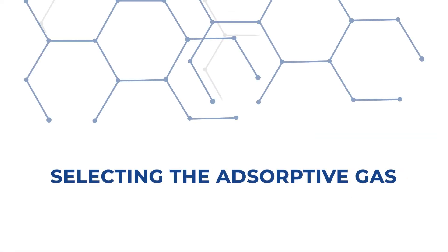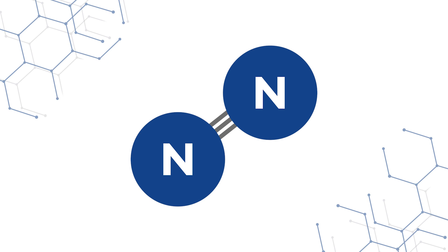Let's start with the first tip: selecting the adsorptive gas. Nitrogen is the most commonly used adsorptive gas for the BET measurement, and krypton is often used for low surface area materials.